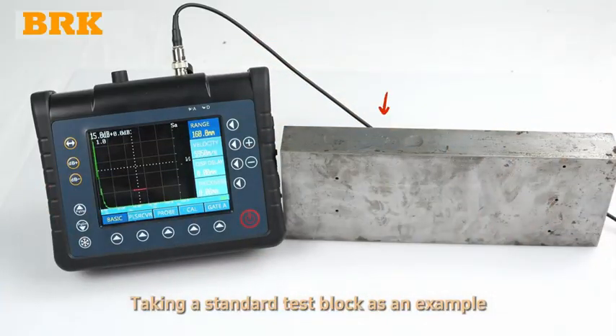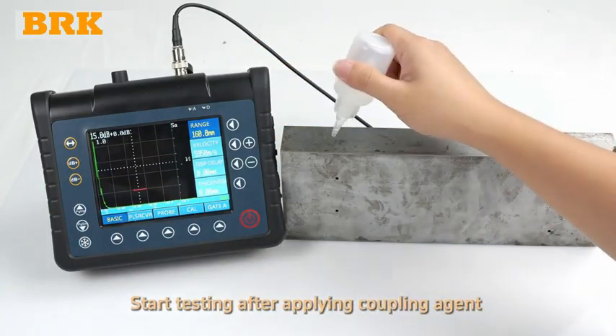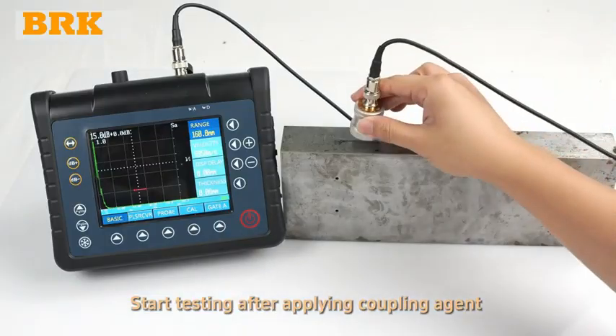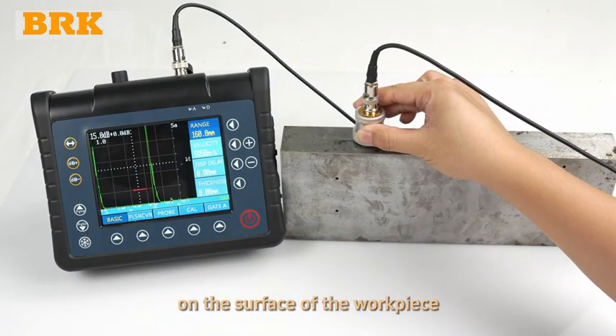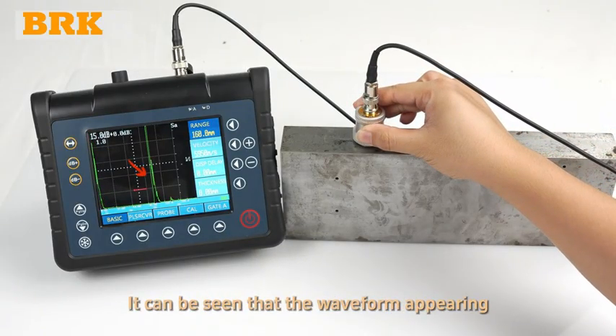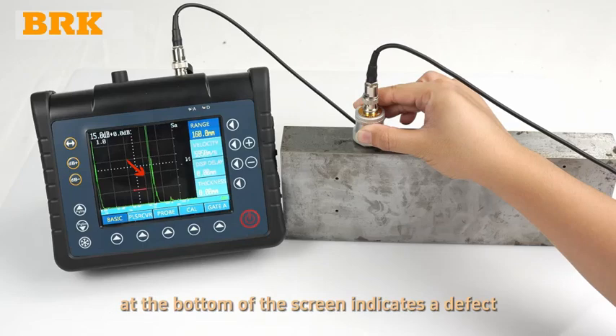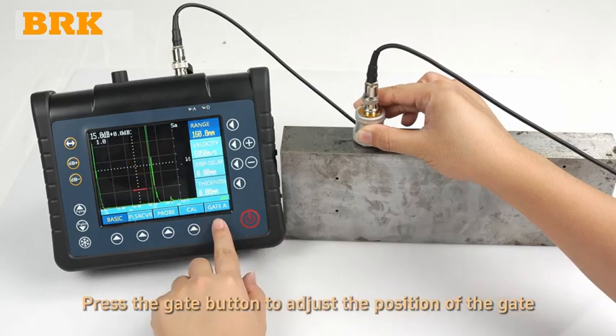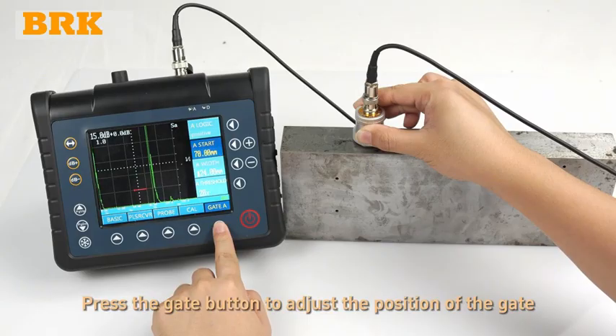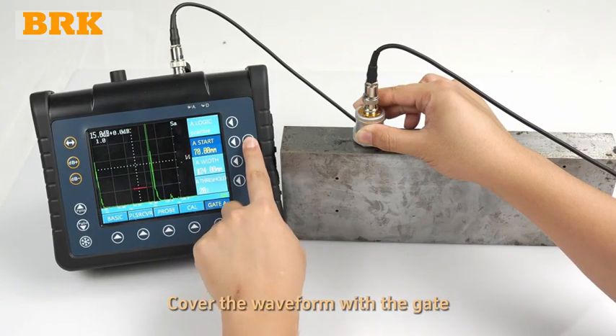Taking a standard test block as an example, start testing after applying coupling agent on the surface of the workpiece. It can be seen that the waveform appearing at the bottom of the screen indicates a defect. Press the gate button to adjust the position of the gate. Cover the waveform with the gate.